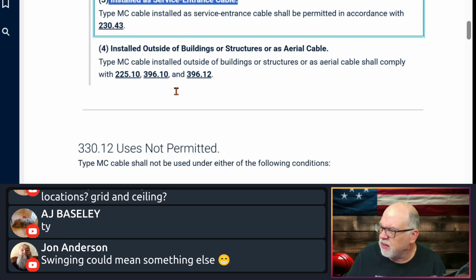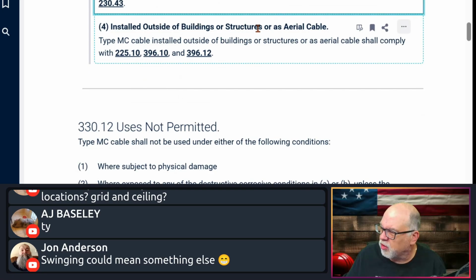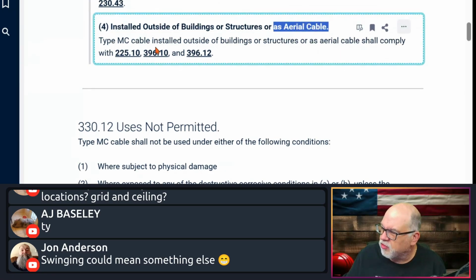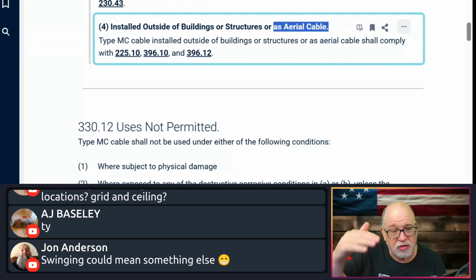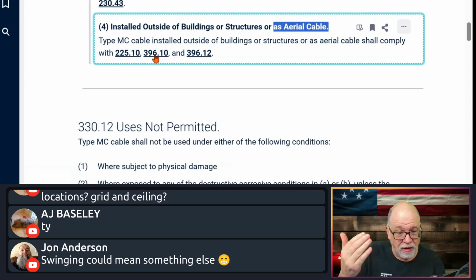And then, of course, installed outside of a building or structure or as aerial cable. MC cable installed outside of a building or structure or as aerial cable shall comply with 225.10. Now, 225 is outdoor branch and feeder applications. Okay. And 396 is messenger. So you got to meet some messenger requirements, right?